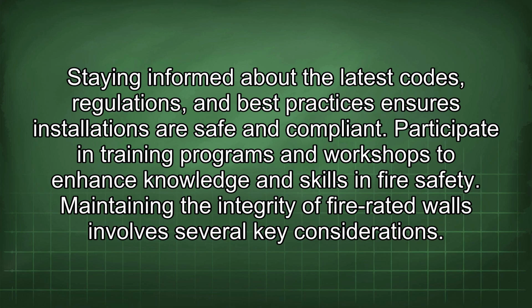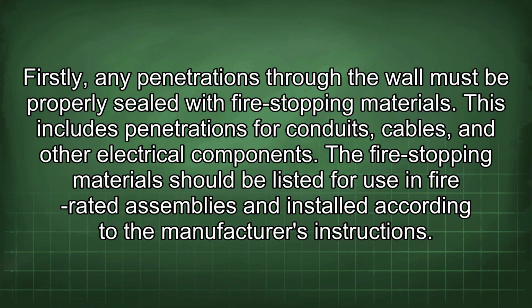Maintaining the integrity of fire-rated walls involves several key considerations. Firstly, any penetrations through the wall must be properly sealed with fire-stopping materials. This includes penetrations for conduits, cables, and other electrical components. The fire-stopping material should be listed for use in fire-rated assemblies and installed according to the manufacturer's instructions.